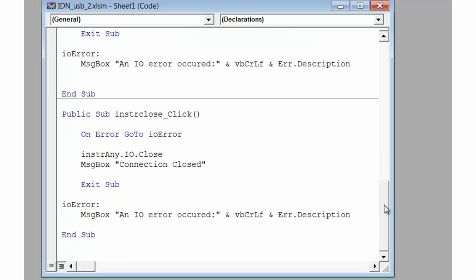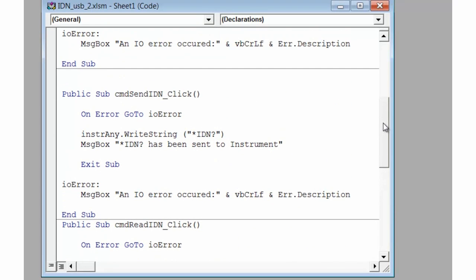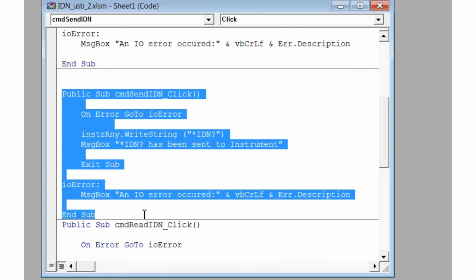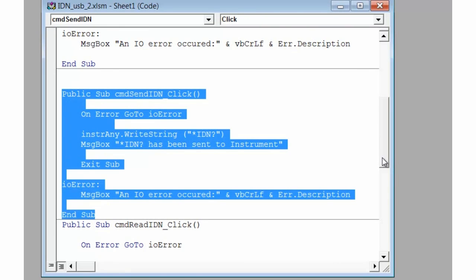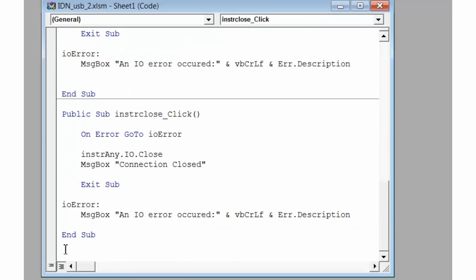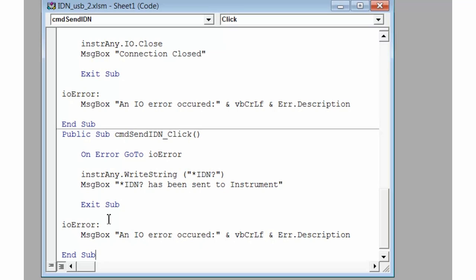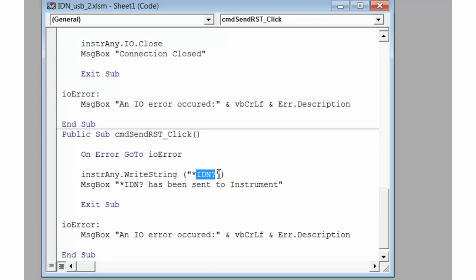I want to show you how easy it is to create one of these subroutines. Let's copy our subroutine that sends the *IDN command — we'll copy the whole thing and paste it in at the bottom of our program. I'd like to change this subroutine to send a reset command, which is the *RST command. We'll change the name of our subroutine to RST, change the SCPI command being sent to *RST, and change the message box text to RST as well. Now we've added a new subroutine in Visual Basic.